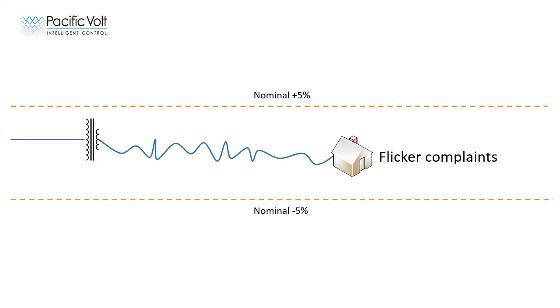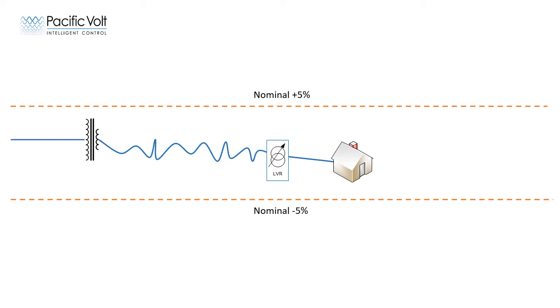Secondly, flicker can also be caused by a rapidly changing load on the secondary side, such as EV charging, a large on-demand hot water heater, or a welder. Note that in this case the flicker is not transferred back onto the primary because it is a relatively small load change. Installing an LVR, preferably close to the building, will mitigate the flicker complaint.